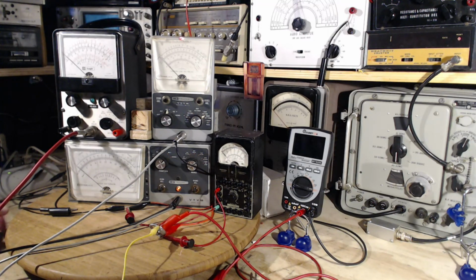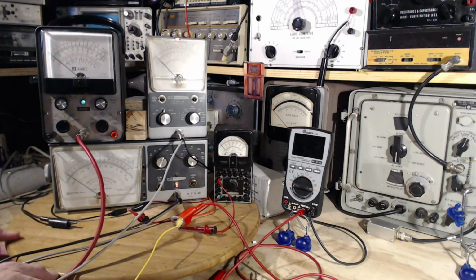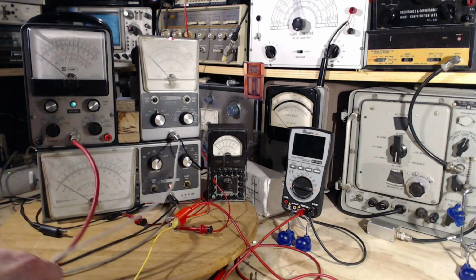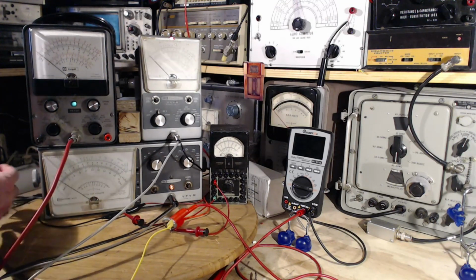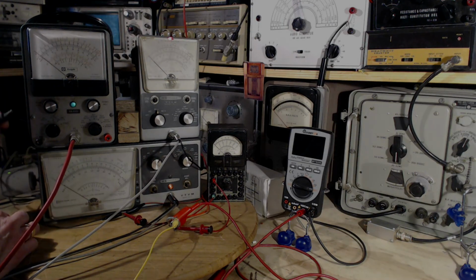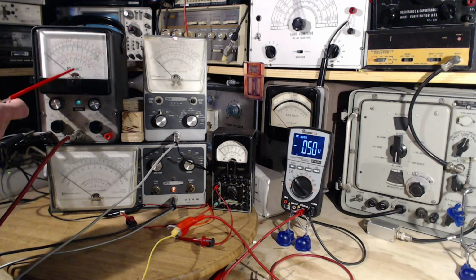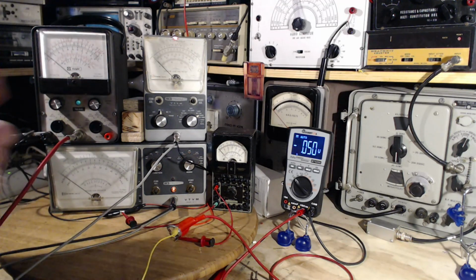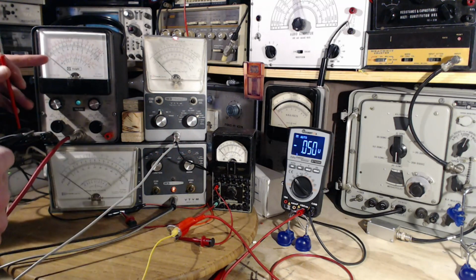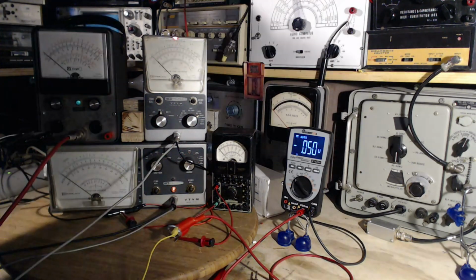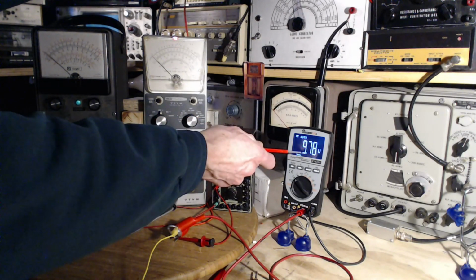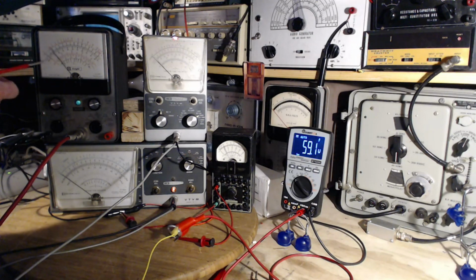And I'm going to want to adjust the DC. Let's see how easy it is. Now I've got this all set up so I can do this. Oh my gosh, I don't have the grounds connected. Okay, so DC calibrate is the middle hole on the back of the cabinet here. You can't see it. I'm going to be sticking this in there and adjusting it for this meter. Let's put 300 volts on here now. Okay, so we watch this one, and watch this guy come up. Put it at 300 exactly. Exactly according to that Mustool.